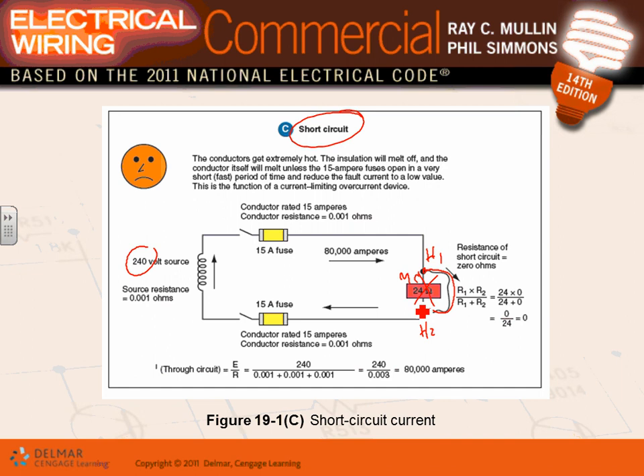Now, if you do that, what happened to the load? Now, the load has been bypassed with a zero impedance. When you put zero impedance in parallel with a load, guys, what do you think you're going to get? Zero impedance, or approximately zero impedance. So this load becomes close to zero impedance, right? Or resistance. The only resistance in the circuit becomes what? The source as well as the cables. That's why the 0.001, this is the impedance of the conductor, it's very small. So if you divide this number, guys, by very small impedance, what do you get?